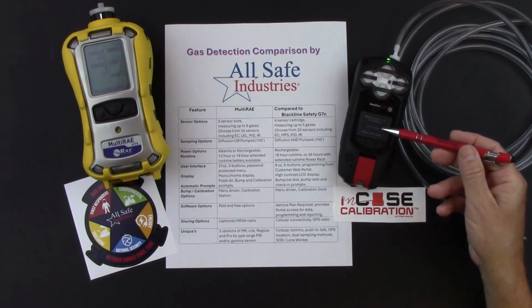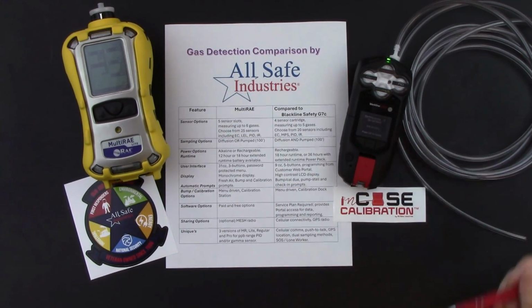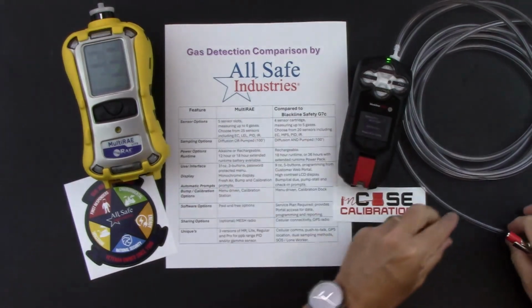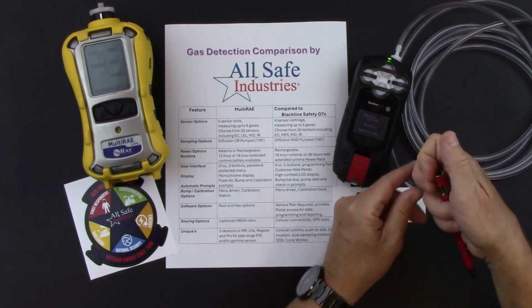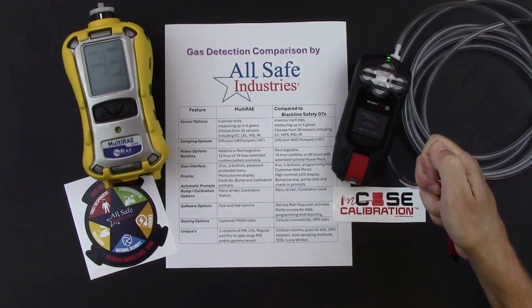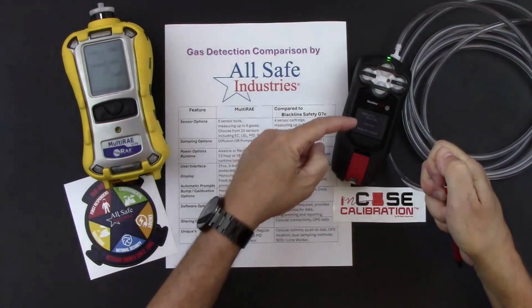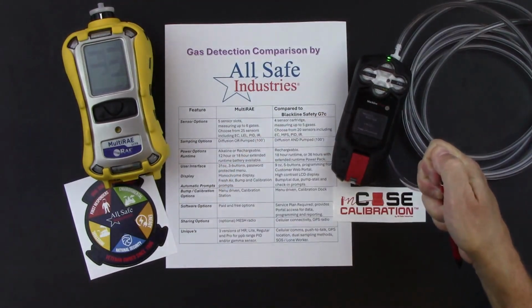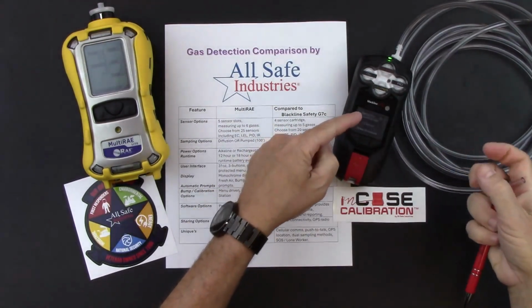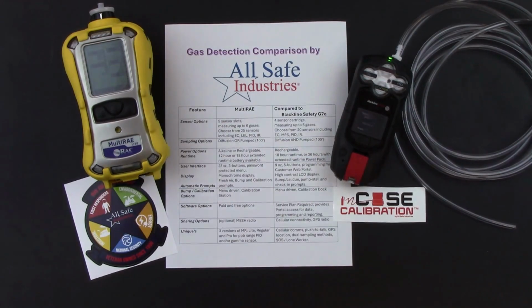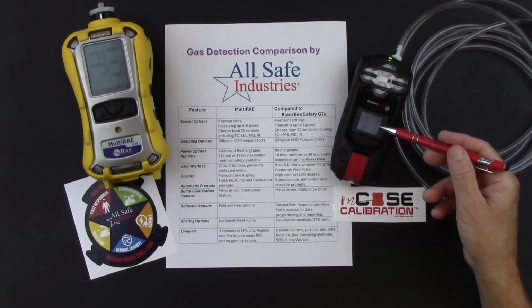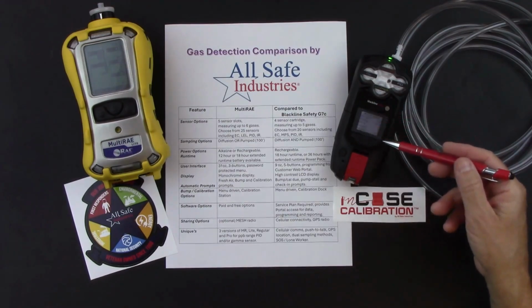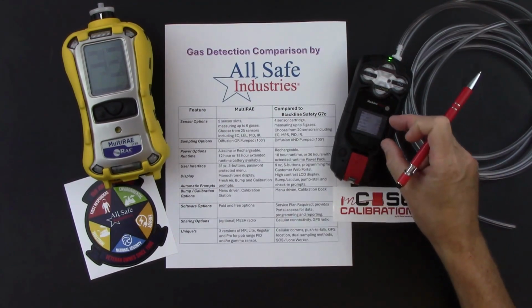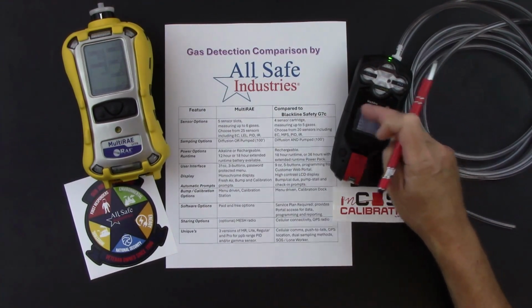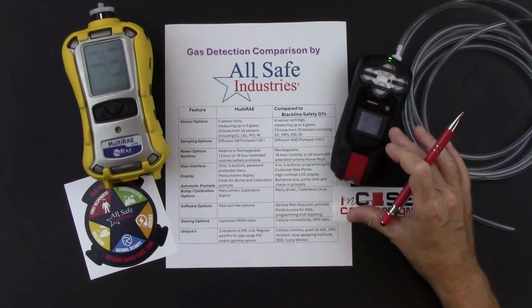Once it ramps up to run speed, it's going to ask me to block my inlet, which it just did. So I'm going to take the end of my tubing and block it. You can see that that's dropped back down to 0, which is a good sign. And now it's asking me to unblock the inlet. Block test passed. And now you can see that the screen has inverted. It's a white background with black characters on screen. This reminds me that now my pump is running.